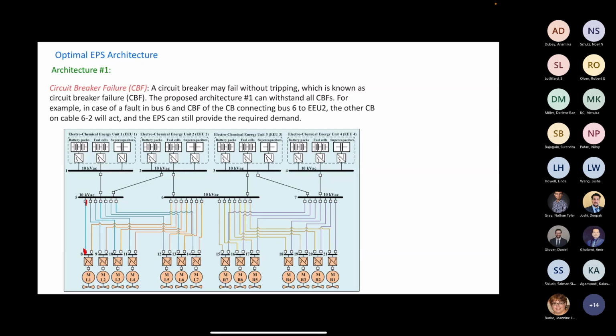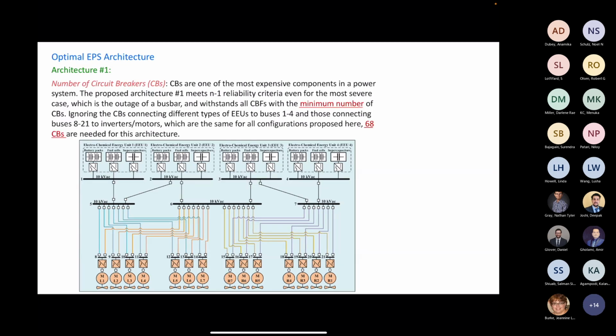Another criteria we used is to minimize the number of circuit breakers, for two reasons: weight and cost. You can come up with other architectures with more breakers, but this is the architecture that is reliable under single contingencies, including circuit breaker failure, and it has only 68 circuit breakers.